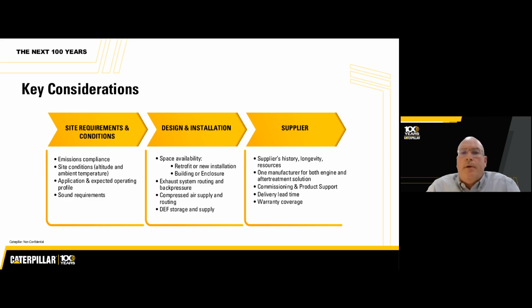Back pressure is another important consideration under the design and installation category. We won't touch on every one of these, but I'll cover a few. We're starting to see stacked enclosures, so the bottom unit may have to be designed for more back pressure capability than the top unit, depending on how all the routing of the exhaust system goes.